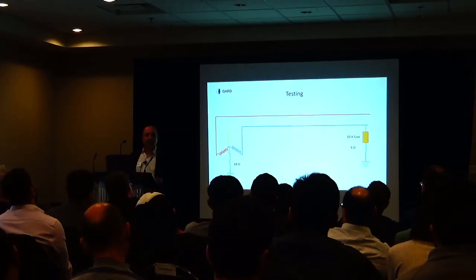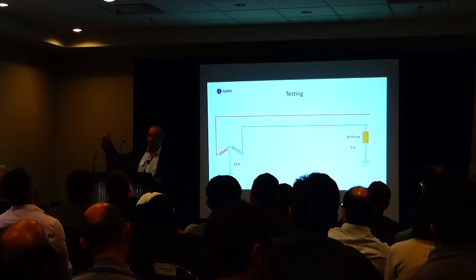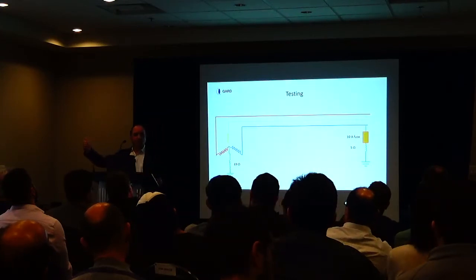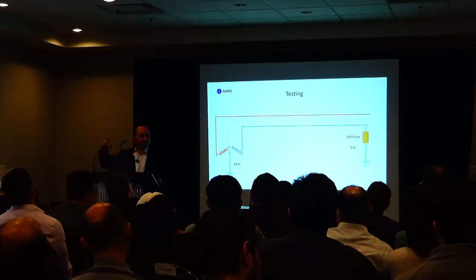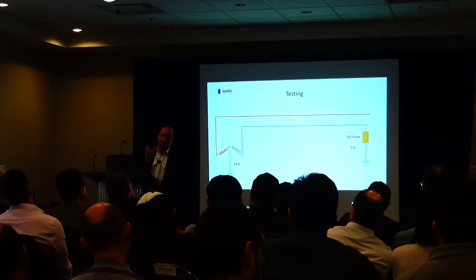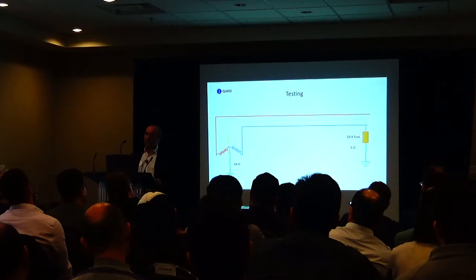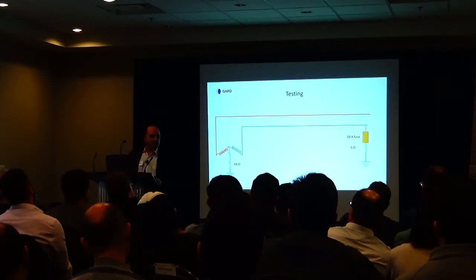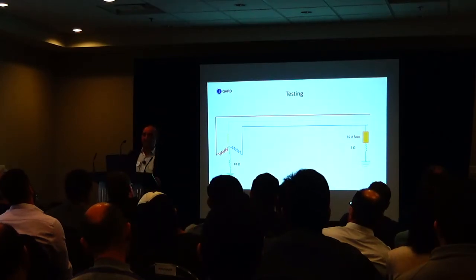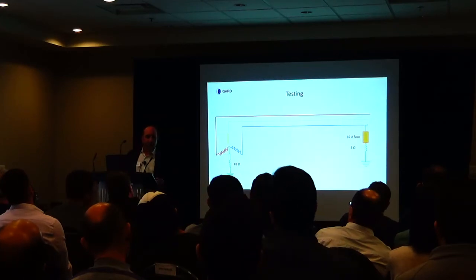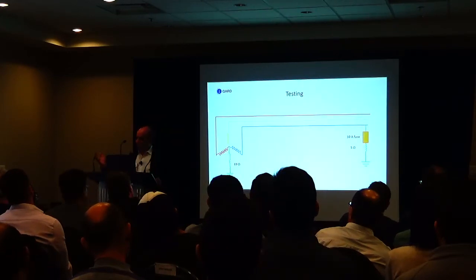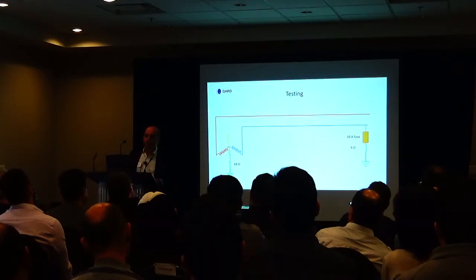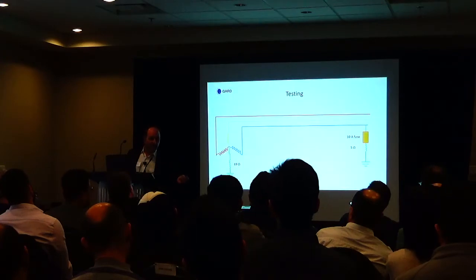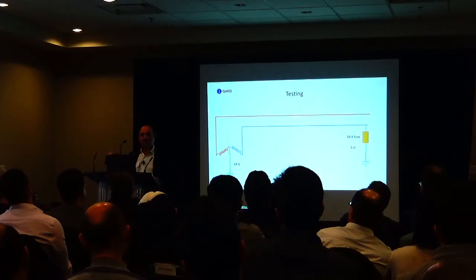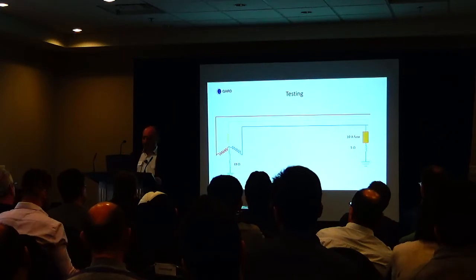Where are you allowed to ground your electrical system? You can ground it at the transformer, because all transformer manufacturers like to have this 1/4 by 2 inch copper link between the neutral bus and ground, the XO and ground. And nobody ever removes it. You're also allowed to ground it at the first switch, and electricians don't always remove that ground. So when you have an electrical system that's resistance grounded, you have to ensure that the system is made to look that way as well.